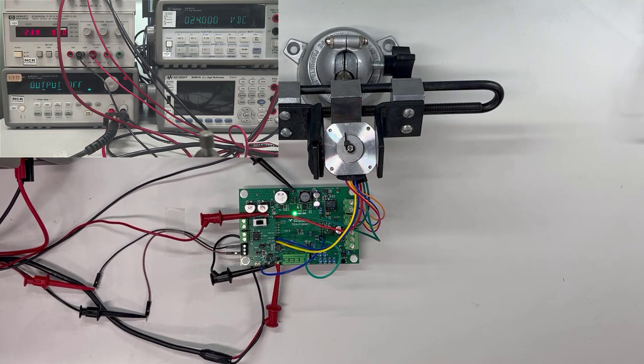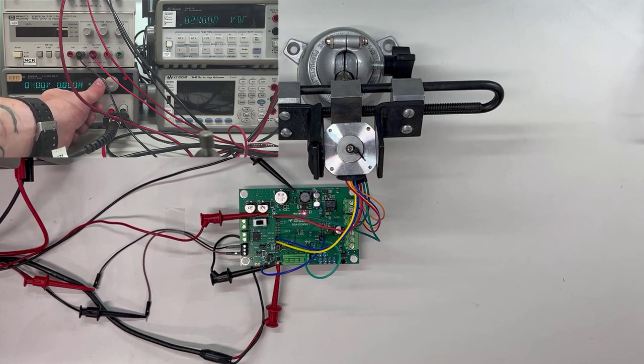Now the other power supply in red is the input voltage to the ISO1212. That power supply will dictate either a 0 degree or 180 degree position. You can see when we first turn it on, there is no movement as the motor is already set to 0 degrees. So to demonstrate it, we use the voltage control to reposition the motor to 180 degrees. And then we will turn the ISO input back on so you can see the motor revert to its original 0 degree position. The ISO input takes priority over any other input, so you can see that the voltage control does not take effect until that power supply to the binary valve is turned off. Then once again, you can see the motor modulating its position to match the input voltage.